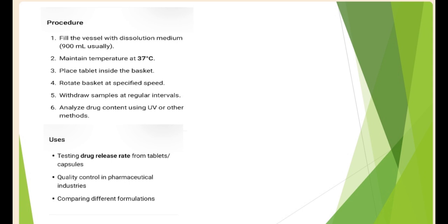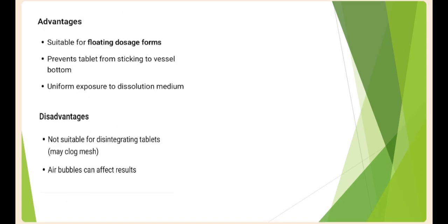Next, move on. Advantages and disadvantages of basket type dissolution apparatus. Advantages: suitable for floating dosage forms, prevents the tablet from sticking to the vessel bottom, uniform exposure to dissolution medium. Disadvantages: not suitable for disintegrating tablets. Air bubbles can affect the results.